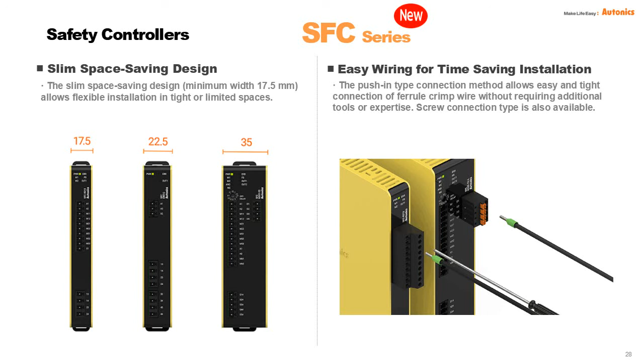We also have built-in off delay outputs and time settings. That means if right now you have a safety controller attached to a motor running, after you press the stop button, the motor does not stop immediately. It will take time to stop. So we have these delay timers. You can set the delay timers to about 15 to 20 seconds. After the motor has totally stopped, then you can release the safety outputs, or maybe you can open the door.